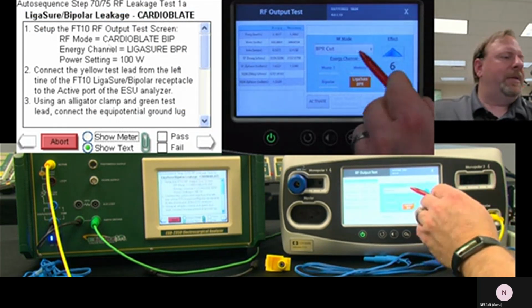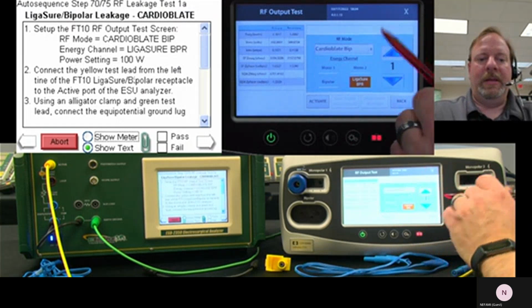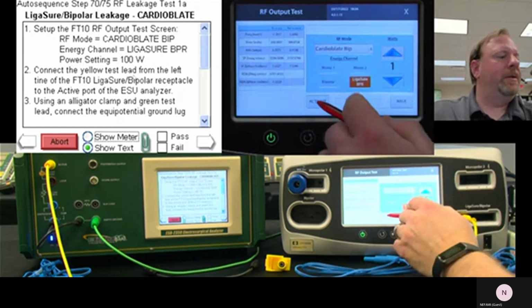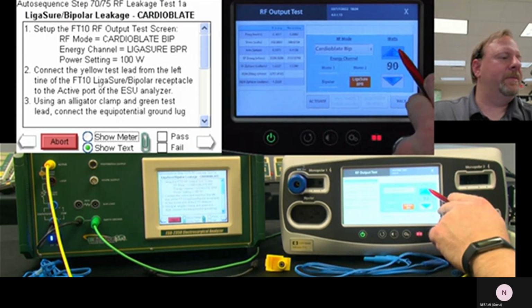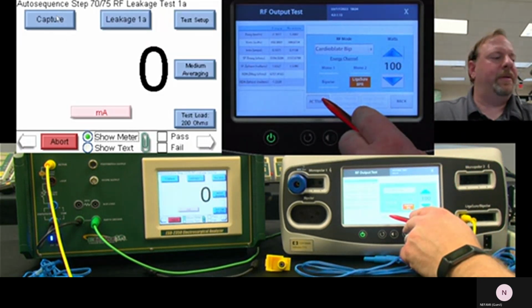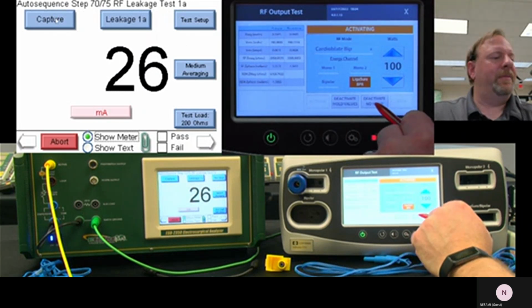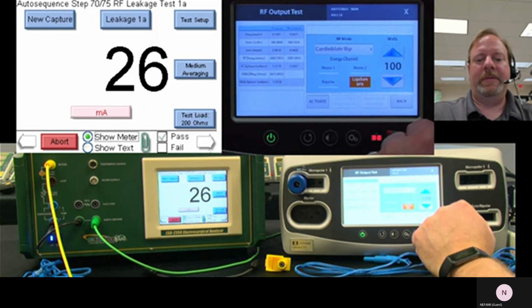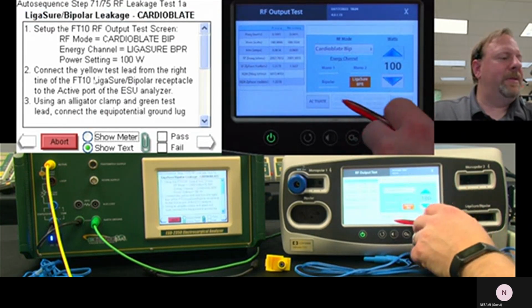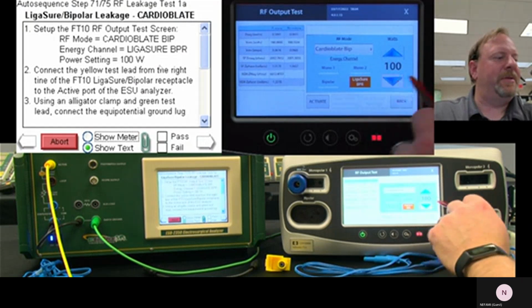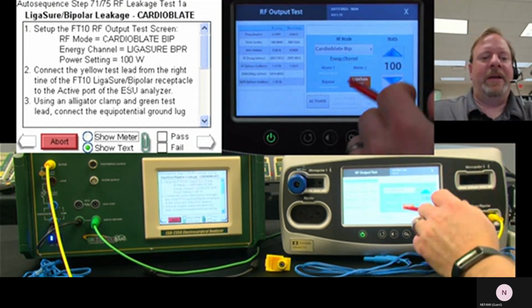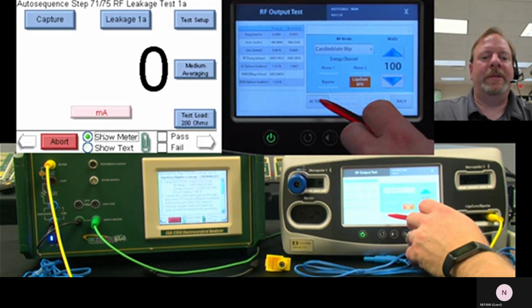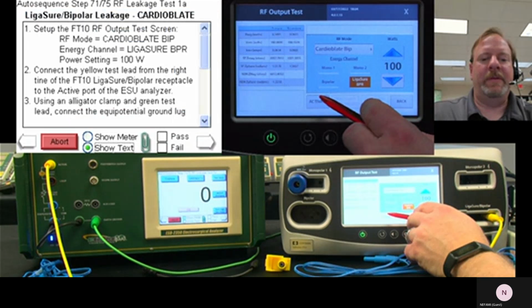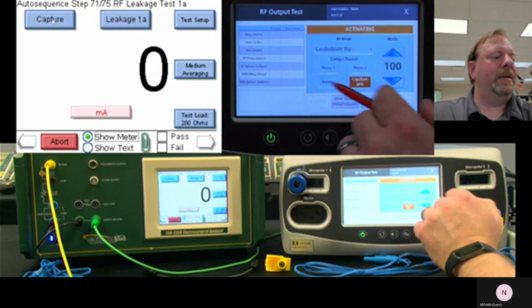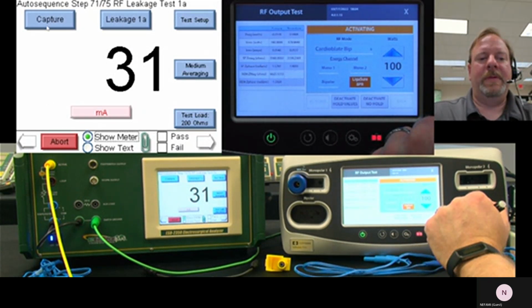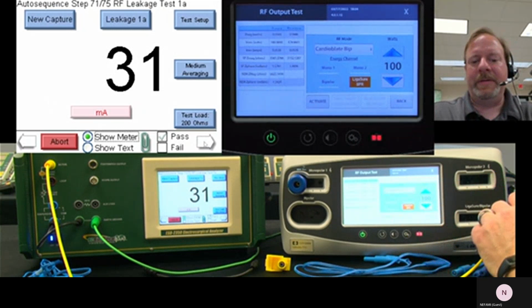Now we set up for cardioblate bipolar. Left tine, LigaSure, there's a pattern here. Maximum setting, 100 watts. Show meter. We got a nice little different beep tone, 26. I'm so used to the Force Triad and the constant tones that those little beeps are foreign to me. Go to the right tine of the FT10. Connections are the same otherwise. Settings are the same. Activate. Capture. Going to make sure it stabilizes.